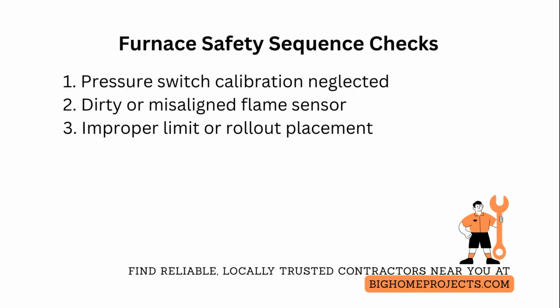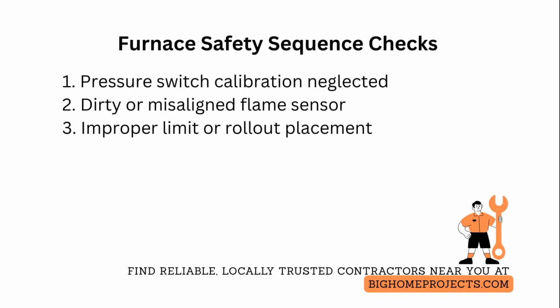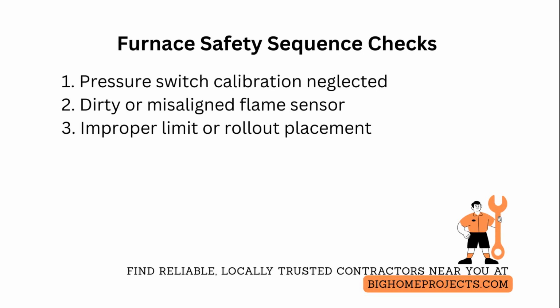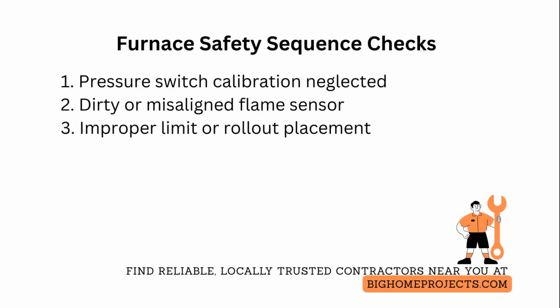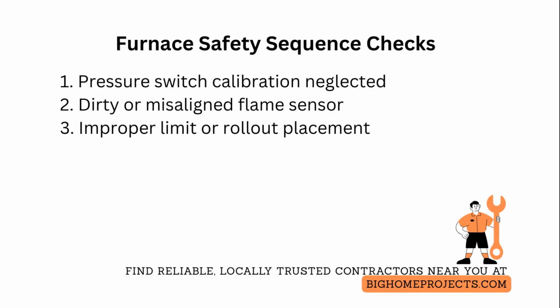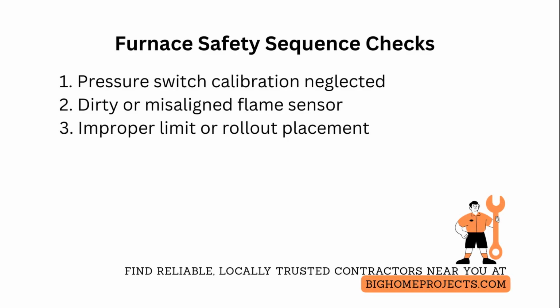meet the furnace specification. One of the frequent installation issues is improper limit or rollout switch placement or wiring, producing nuisance lockouts or unsafe blower starts. Correct it by confirming switch location against the heat exchanger, testing switch trip temperatures, replacing frayed leads with heat-rated wiring, and ensuring the control board inputs are properly pulled up or down per the wiring diagram.